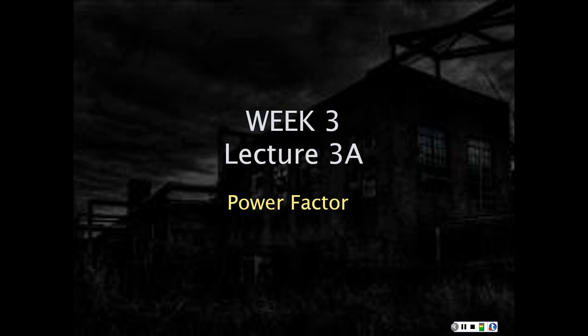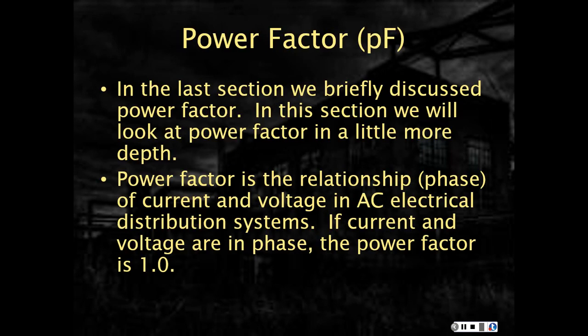This is the first lecture, or lecture 3A, and we're going to cover this week in more depth power factor. As you recall, in the last section we discussed power factor. Now we're going to take a look at power factor in a little more depth. Power factor itself is a relationship or phase of voltage and current in an AC electrical distribution system. If the current and voltage are in phase, the power factor is 1. But very typically they're out of phase. And as we recall last time, this was because of inductive loads. This leads to a power factor of less than 1.